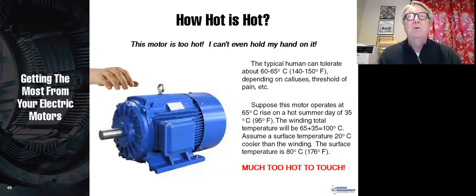But the biggest issue is the insulation. The insulation is specified by NEMA. If you look at NEMA MG1, which is the standard for motors, there's a part 30 and a part 31. Again, I'm going to cover this in more detail next week or the week after. But part 30 is for a motor that's not on a VFD, and it specifies that the insulation should be 1,000 volts. Now we're talking about low voltage here. We're not talking about medium voltage, but on a 230 or 460 volt motor, the insulation is 1,000 volts to the PWM signal.